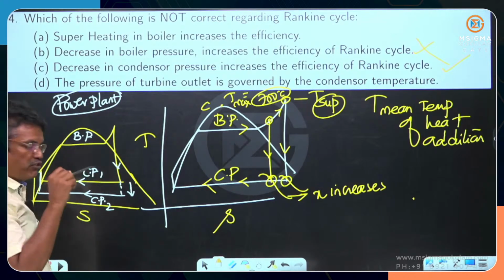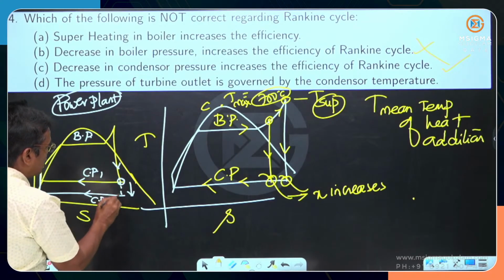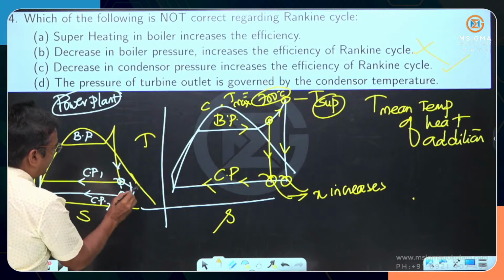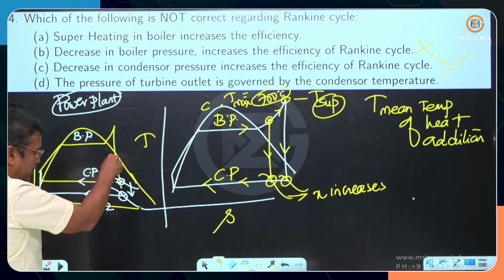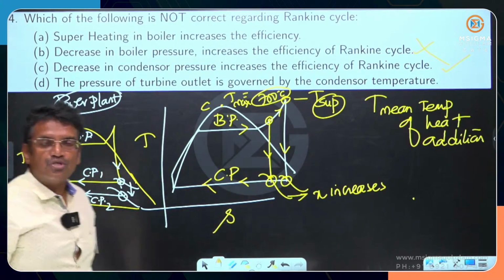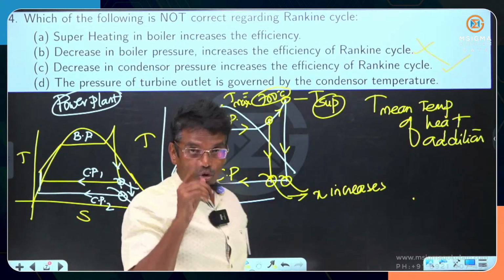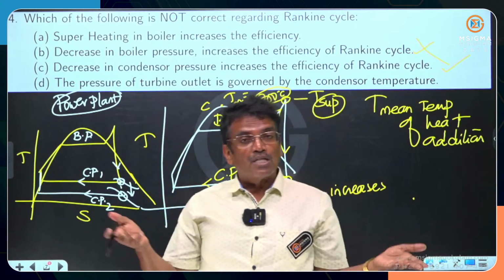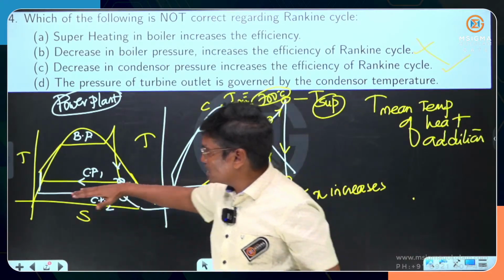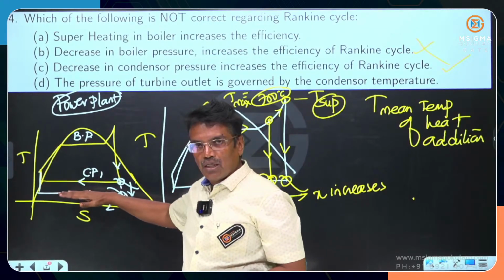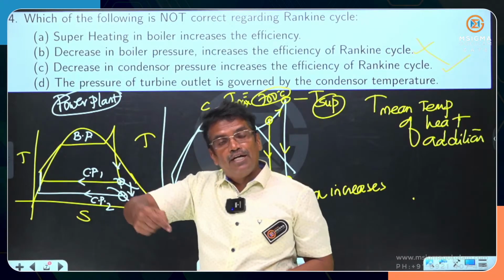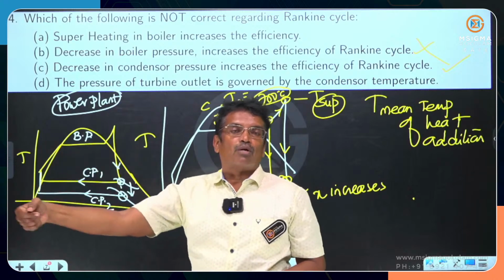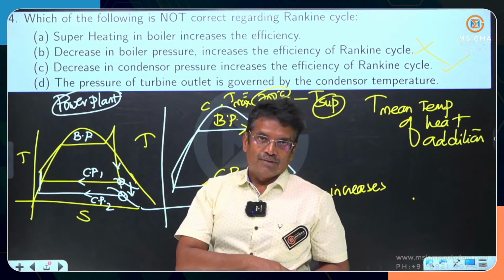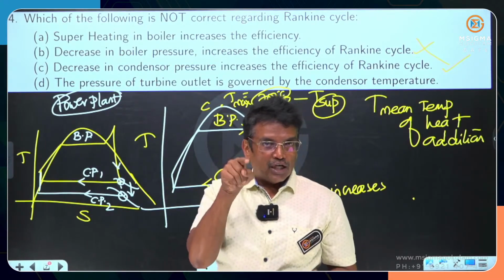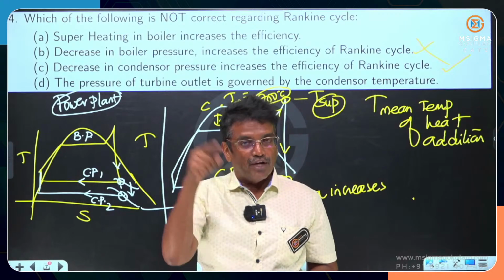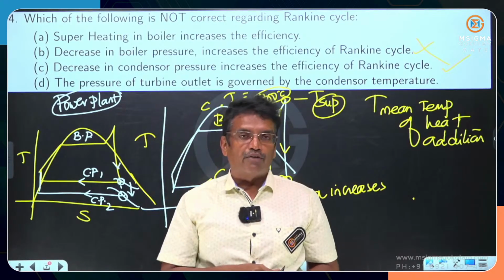But there is one catch, there is one condition. As you decrease the condenser pressure, the dryness fraction of the steam goes to dangerously low levels, which may cause turbine blade erosion. And one more thing, we can't decrease the condenser pressure like anything, because the condenser pressure we provide mainly depends upon the cooling water temperature we provide into the condenser. See, because into the condenser there is a coolant going, cooling water. From where is it coming? From the river, or from the cooling tower.